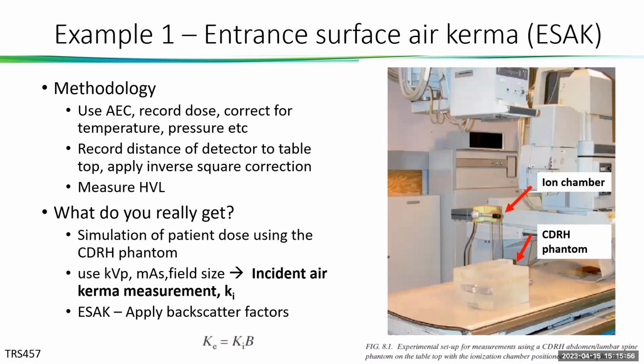Just a few examples. For example, if we're measuring entrance surface air kerma here, according to TRS 457, this is the setup that you need. You have an ion chamber, and you have a phantom here, and you need to use the phantom to enable the AEC to work, to simulate a more realistic patient exposure setting.